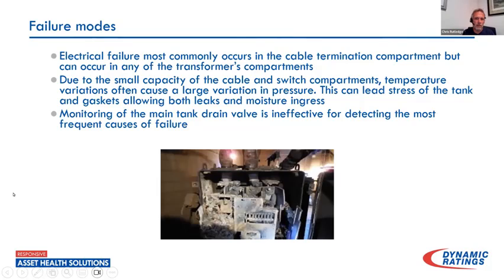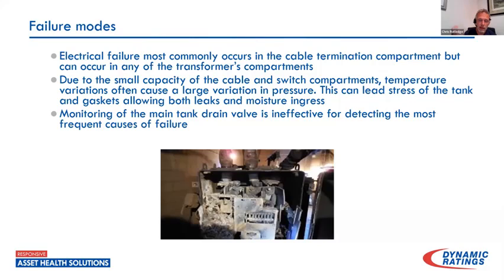Due to the small capacity in these switch compartments — about eight gallons of cable oil — when you have that high-energy event in there, there's just nowhere for it to go. There's no pressure relief device. We're going to ignite that oil from the quick thermal increase, blow that door out, blow that tank out.